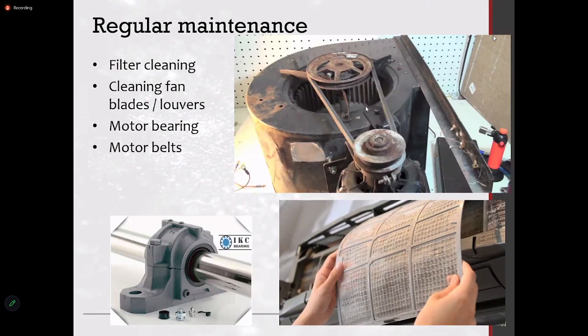So basic maintenance of this type of ventilation system, even part of an air conditioning system. Wherever air is circulated, you will not get pure air coming into the system. You'll have to install a lot of filters and a lot of insect control to ensure that no foreign particles are entering the space. So the disadvantage is they could get clogged.